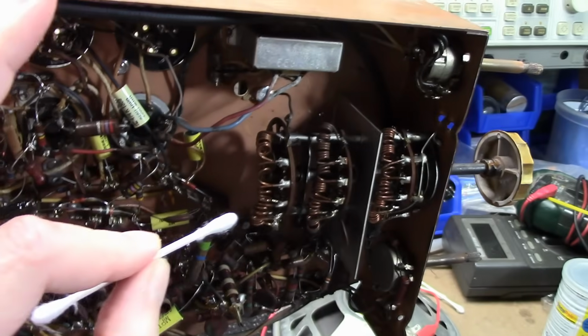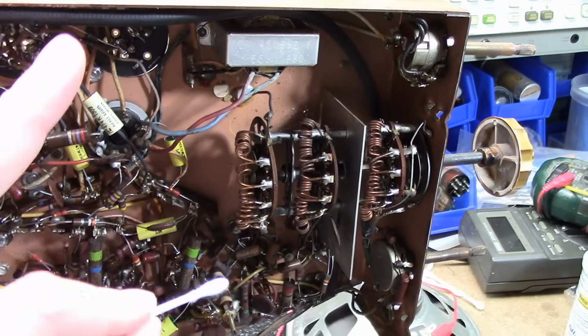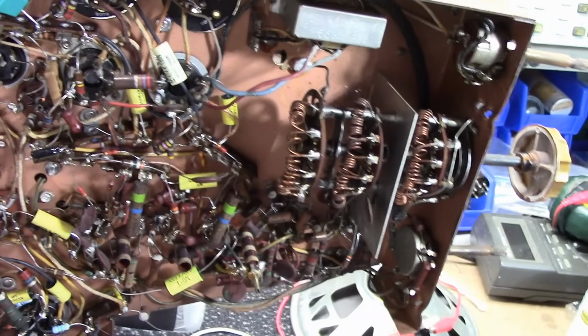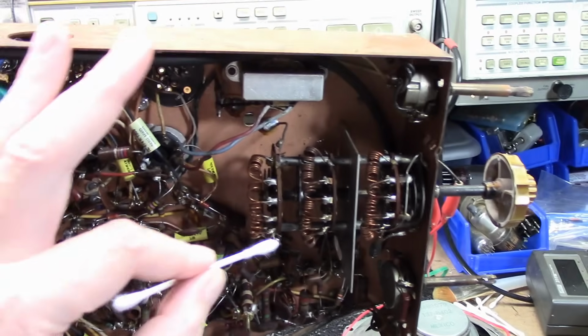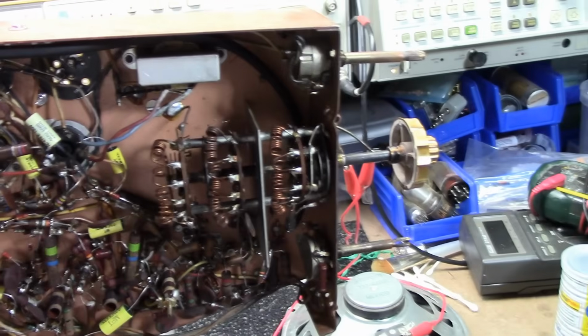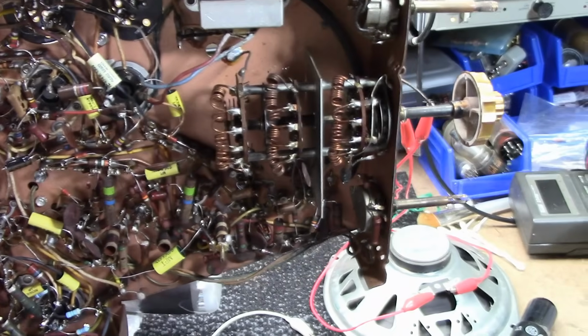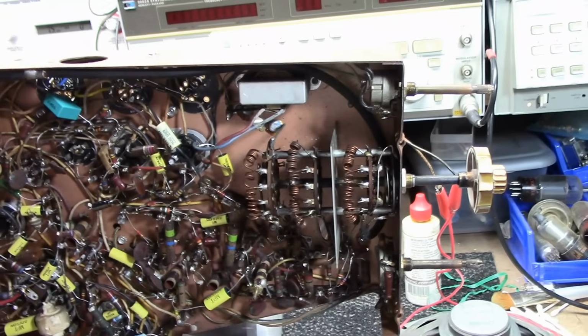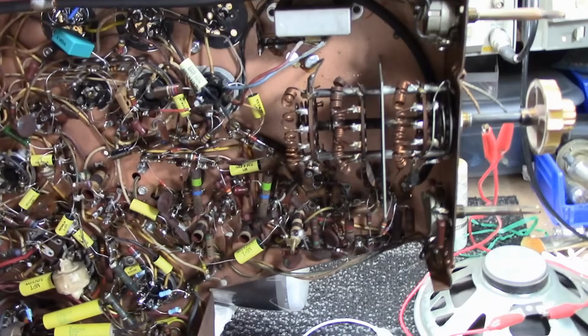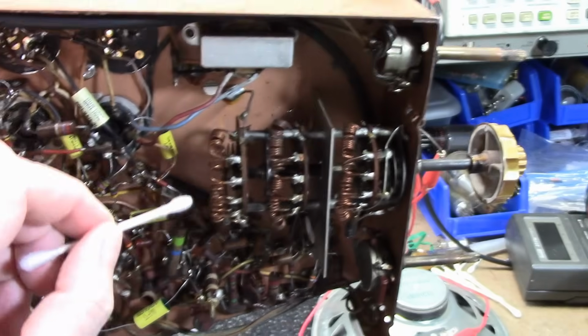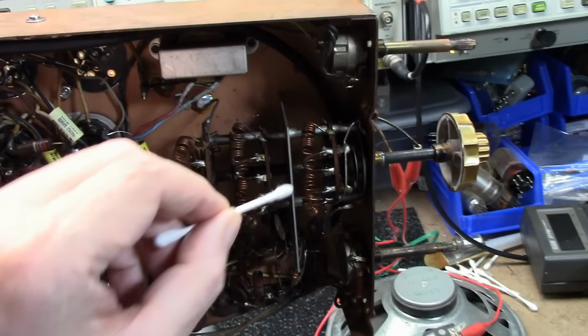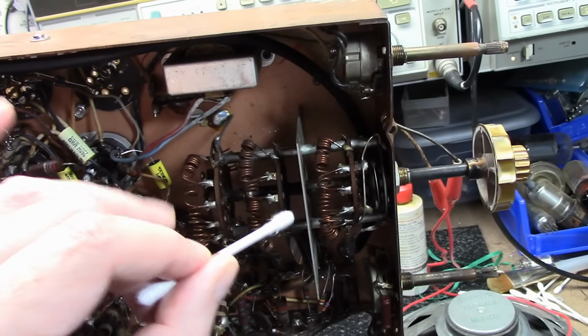They are silver plated contacts back there, and put some pressure on this and press it against the tracks, and then rotate the switch around, and you'll see this will start to get black as some of the corrosion comes off. I think you'll have much better luck and much better success doing that. Just be careful when you do that not to bump into or move these coils. They're pretty heavy gauge wires, so they're not super fragile, but you don't want to mess with those.